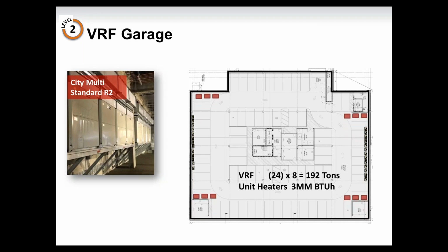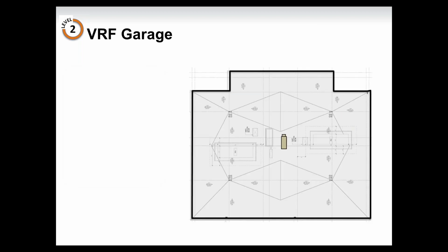The important thing with this design is by moving the outdoor units into the parking garage, we do not require the hyperheat units for the low ambient performance, so we save money on that portion of the project. Similar to the rooftop design, the only thing that we would have on this solution on the roof is the 6,000 CFM DOAS unit, and most likely would not even require rooftop screening because it's dead center in the middle of the building and very small.